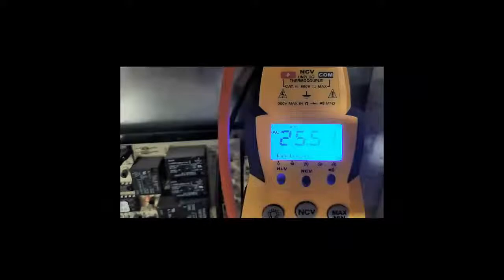If you have correct mainline voltage to the unit, the door switch is properly engaged, the low voltage fuse is good, and the transformer is good, you will have 24 volts between the R and C terminals. And it is okay if your voltage reading between R and C is plus or minus 3 to 4 volts. Now let's take a look at the low voltage fuse. It is typically a 3 or 5 amp fuse, and it protects the low voltage circuitry from any short circuits or voltage spikes. If this fuse is bad or blown, you will not get 24 volts between the R and C terminals.